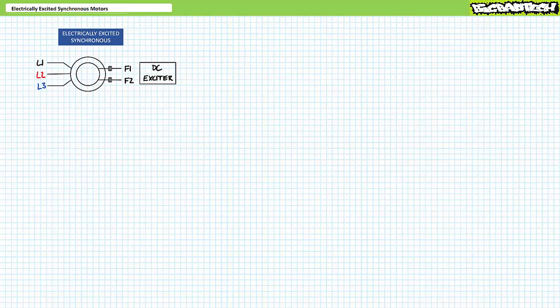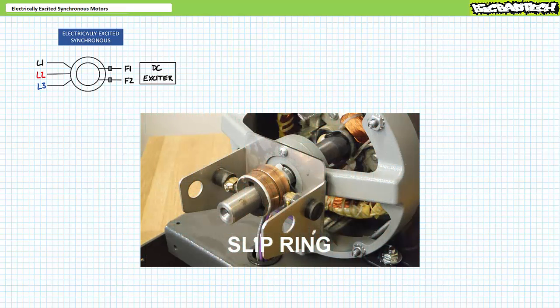How does one send electricity using two wires to something that revolves 360 degrees without twisting the wires into a knot? The device that allows one to do so is known as a slip ring. A slip ring is a means of electrical connection between a rotating and a stationary member. The most basic configuration takes the form of conductive rings on the rotor shaft, which provide electrical contact to the rotor coil. Stationary conductive brushes held in place by a spring and brush holder ride along the conductive rings such that the field coil on the rotor maintains electrical contact with stationary electrical inputs regardless of orientation. Brushes and slip rings require regular maintenance and will eventually wear out and need to be replaced. This adds an operational expense to electrically excited synchronous motors not encountered with squirrel cage induction motors.